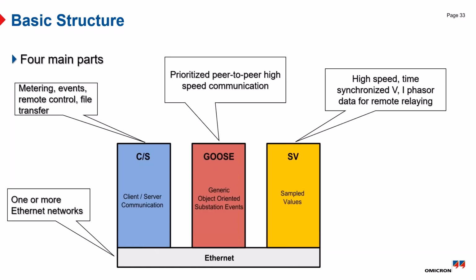One of the other services is sample values. Instead of sampling the voltages and currents and doing an A/D converter at the relay, we do all that at the merging unit, and then we send a sample value stream. So basically a stream of voltage and current samples, put on the network, and any device that's interested can subscribe to that stream and use it in a trip decision, a time coordinated, high speed, real time stream of samples.